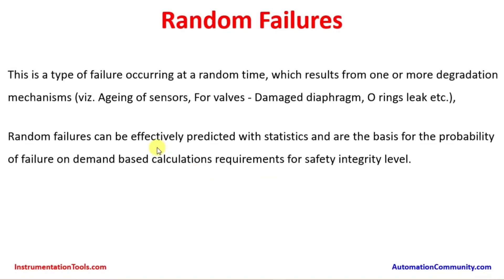Random failures can be effectively predicted with statistics and form the basis for probability of failure on demand calculations and safety integrity level requirements. Although the individual failure itself is random and cannot be predicted, patterns can be identified over many years across different industries performing similar operations or in similar environmental conditions, and the nature of failures may be typically similar from plant A to plant B.